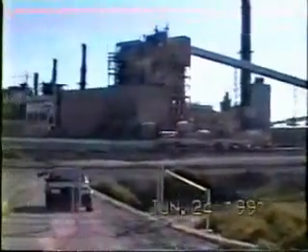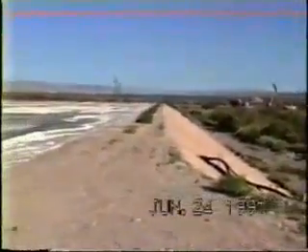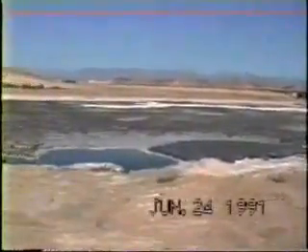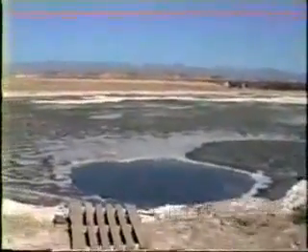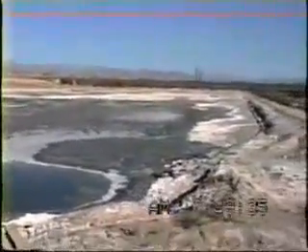At a large coal-fired power plant, we're here to do a demonstration of the Toyo submersible agitator pump. What we'll be doing is attempting to move fly ash out of this pond coming into view here. We can see a hole right in front of us where a front end loader has tried to dig the material out. This is the hole it created after 2 hours.